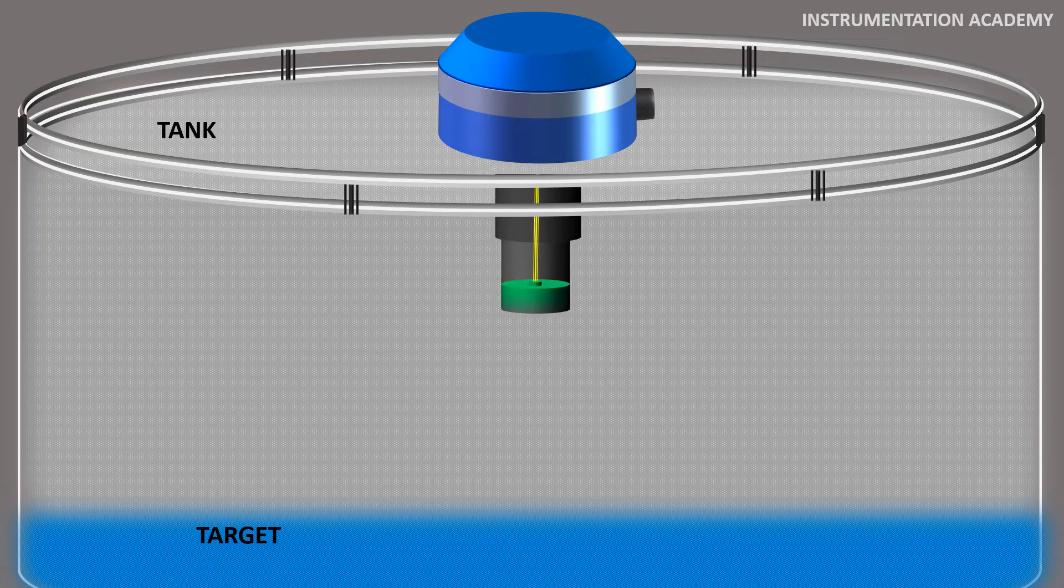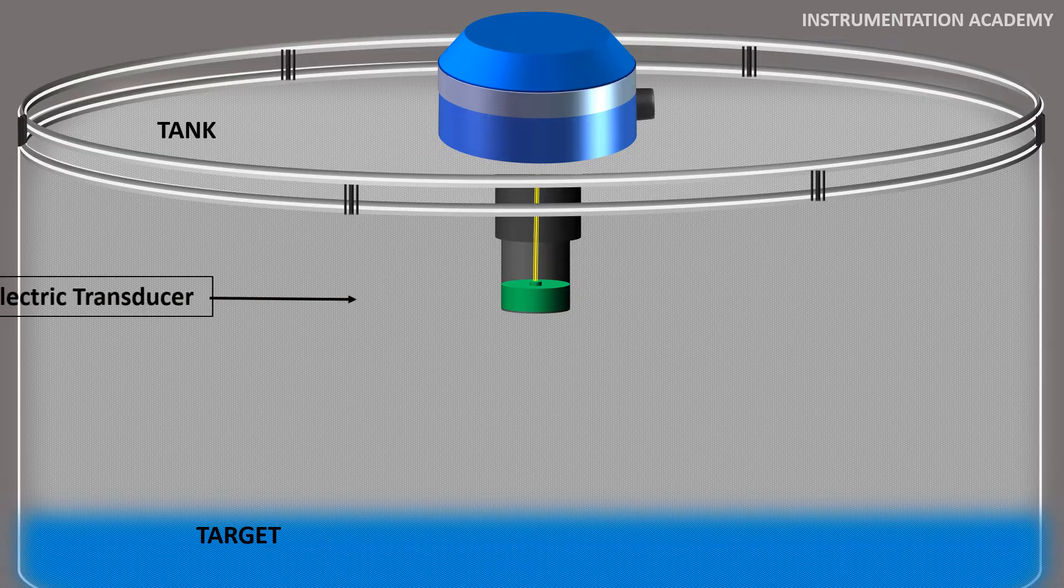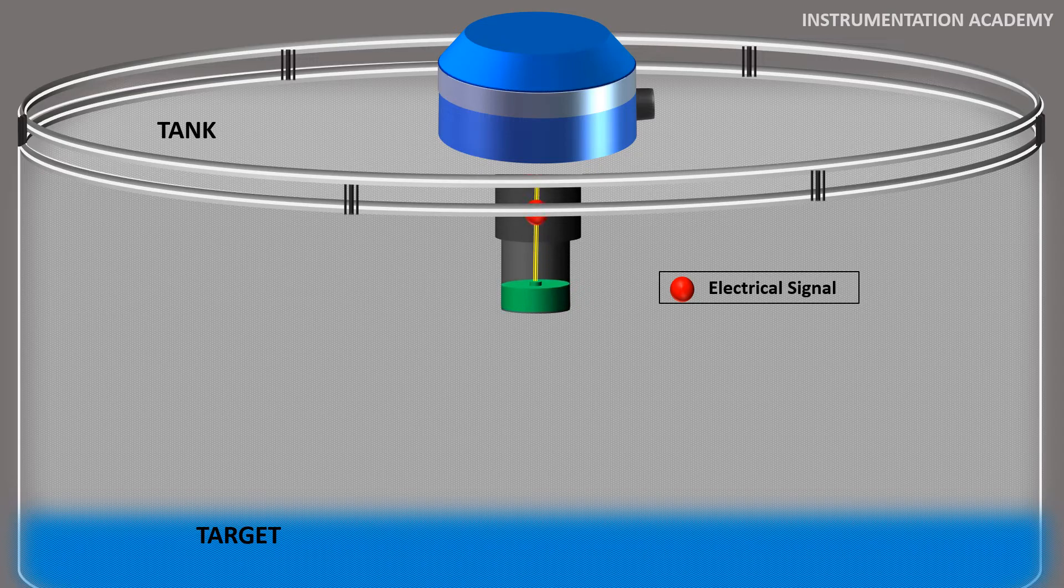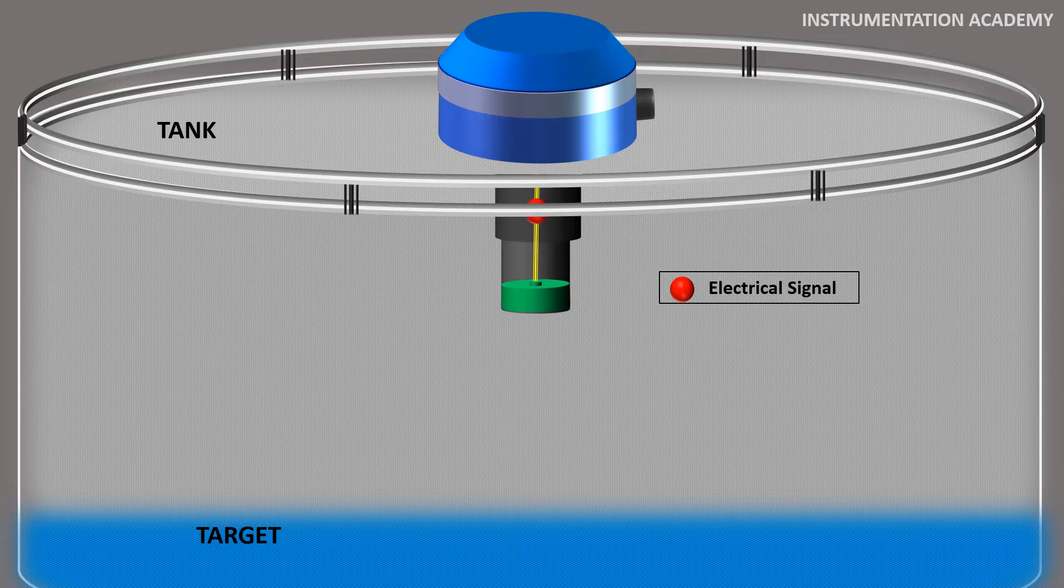The ultrasonic level transmitter consists of a piezoelectric transducer, which vibrates when an electrical signal is fed into it and converts the electrical signal into sound energy. These sound waves are emitted onto the target at a given rate, for example 5 times per second.